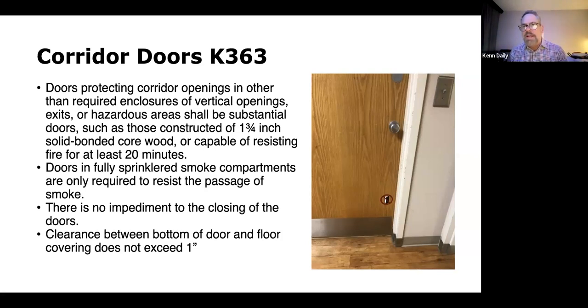Now for the gaps, by the way, it's a 1/2 inch all the way around, an inch at the bottom. There is a QSO notice back from 2007 that says in a fully sprinkled building, you are allowed a 1/2 inch gap to resist the passage of smoke, which you and I probably both agree that 1/2 inch is pretty big when you talk about smoke. But being that we are fully sprinkled, it provides a lot of protection. And it would reduce the amount of smoke that was going to be generated. So that must be the thinking of CMS, and that continues today. But the biggest issue, again, is closing and latching. That door is resisting the passage of smoke only if it closes and latches.